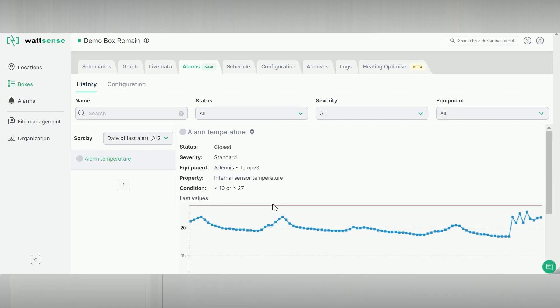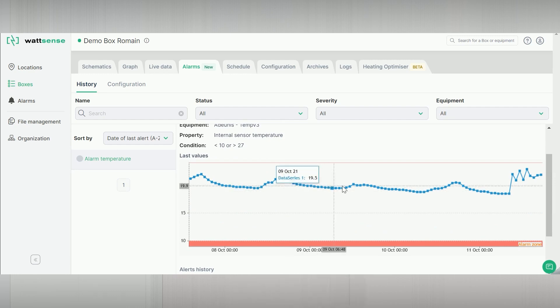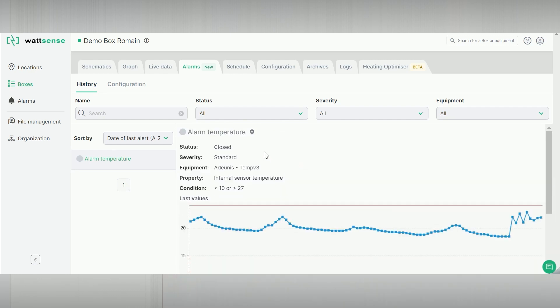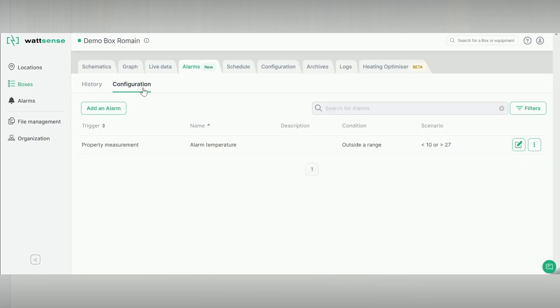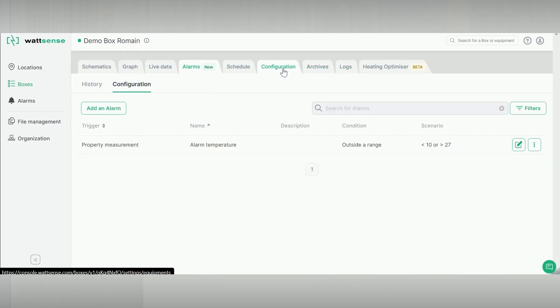Data integration is carried out via REST API or MQTT. 4G SIM card is provided. The box can act as a local BACnet IP or Modbus IP gateway if you prefer a local integration.